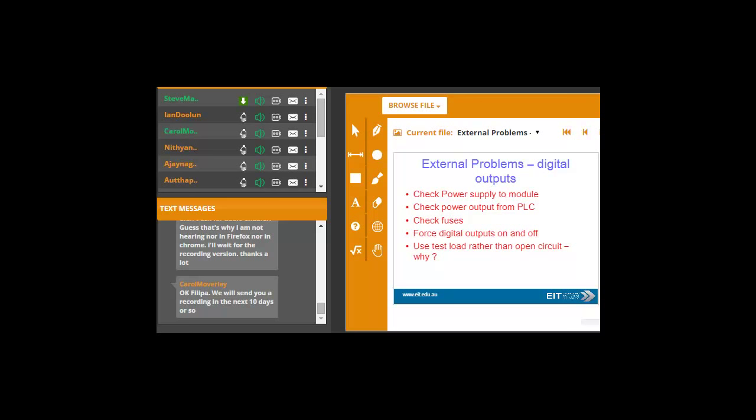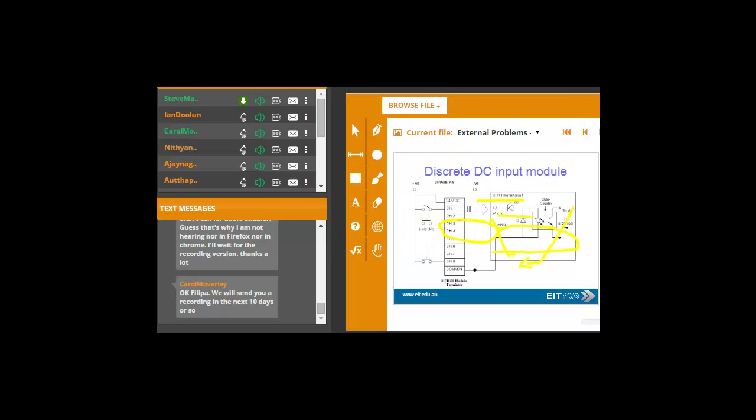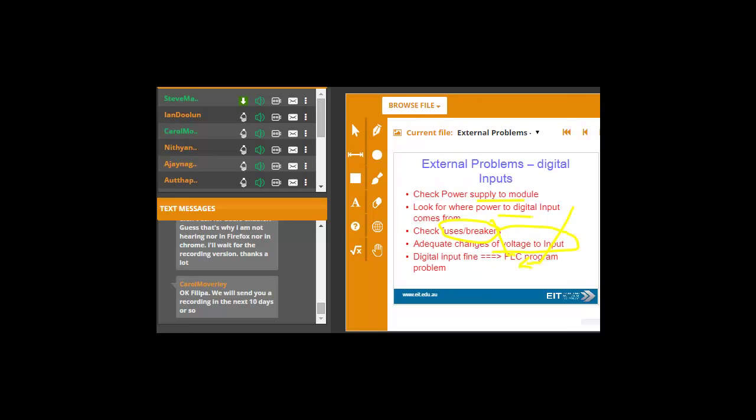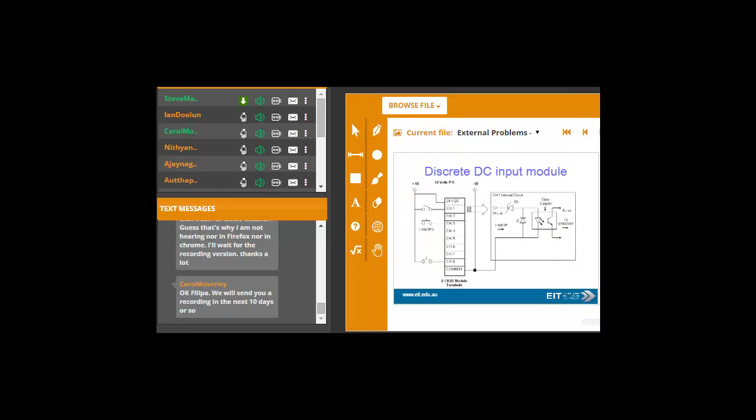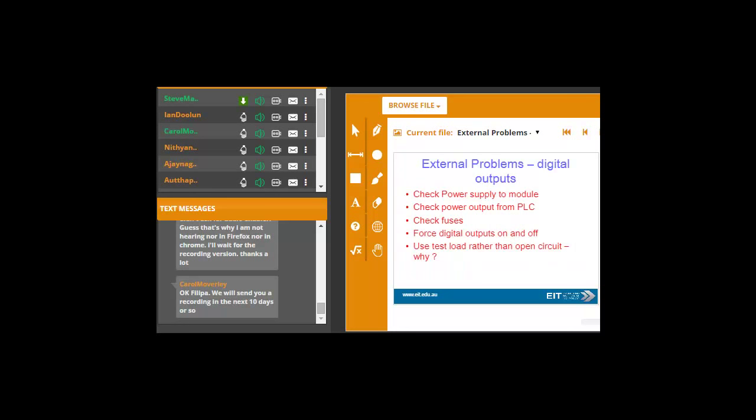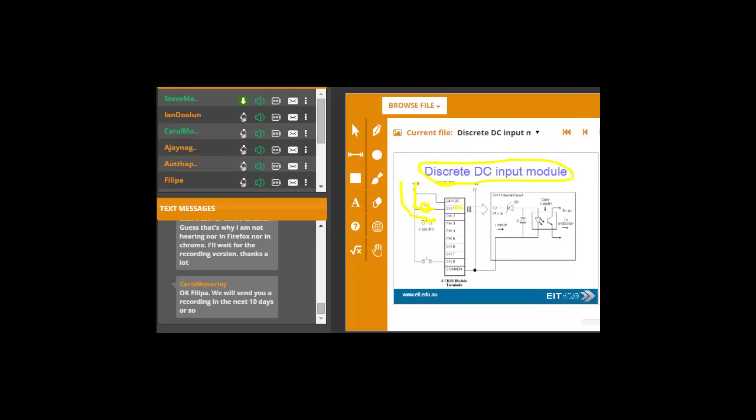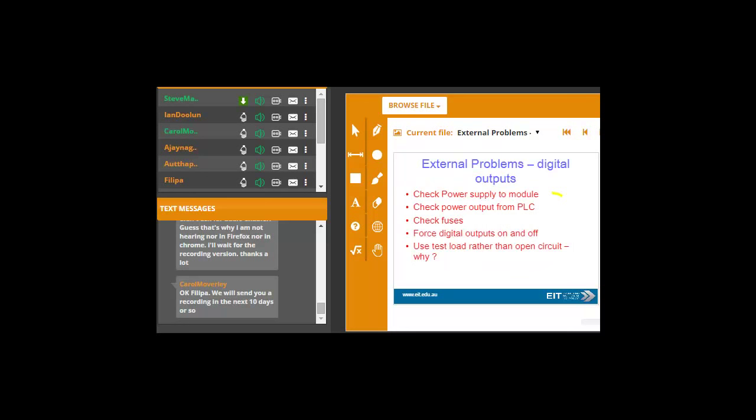And these are often due to proximity detectors having a low resistance, so you have enough leakage coming through to actually bias your input to be on, even though the output voltage is off. So watch out for subtle little problems like that. Watch out for them. Big issue. The other little issue here, by the way, just to protect your cards, some of the cheaper cards don't have optical isolation. It's a very good investment to have optical isolation. Just make sure your cards have optical isolation for the inputs. So leakage current can be an issue.